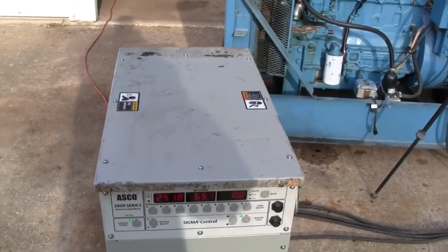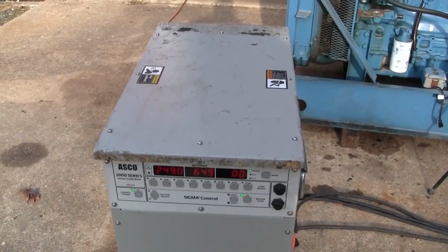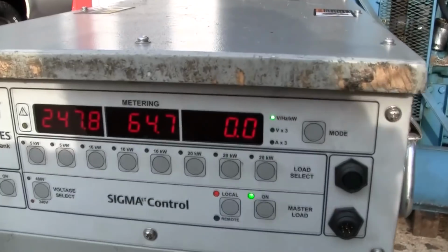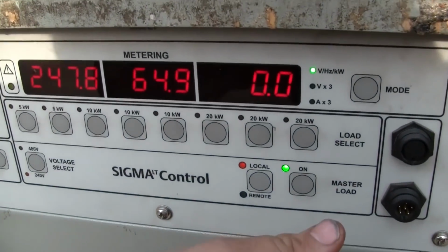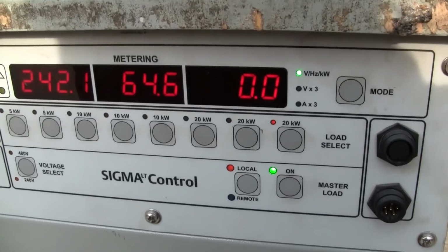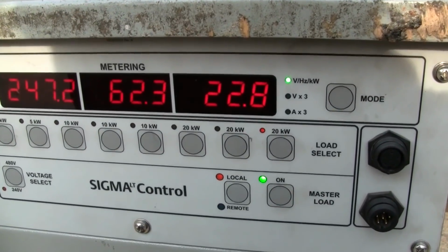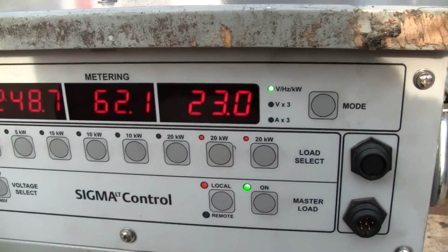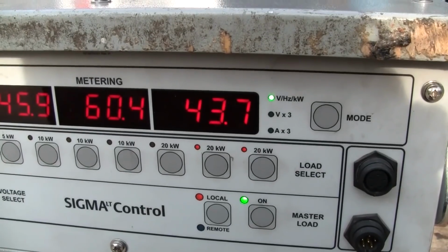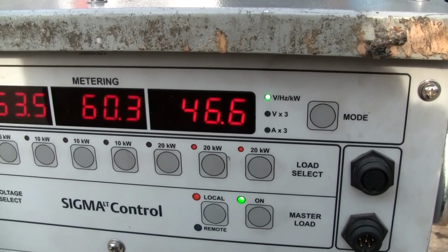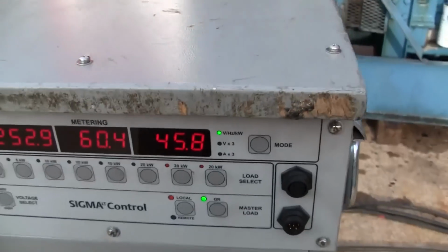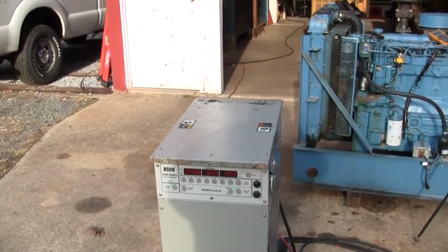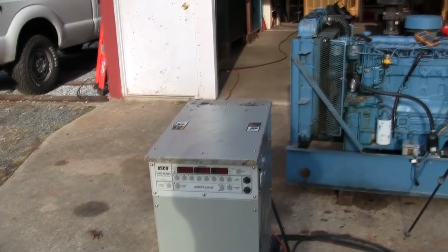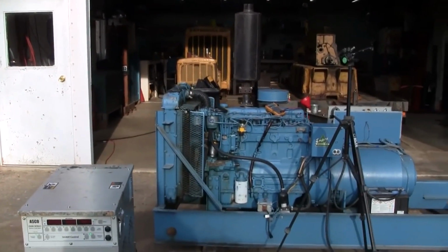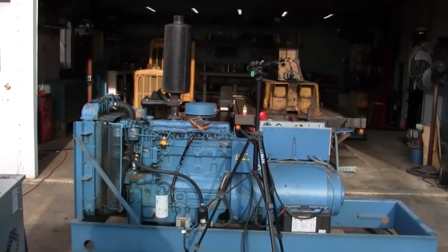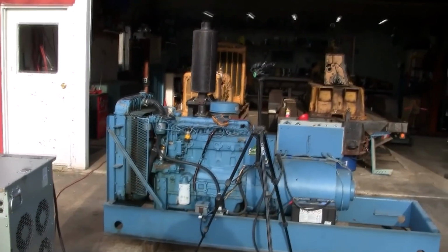So what are we at? We're at, wow, 65 hertz, pretty near. We'll call it 65 hertz. Let's put full load back on it. Yeah, full load brings it back down to 60.4, 60.5. So that's 4.5 to 5 hertz droop. That's unacceptable.